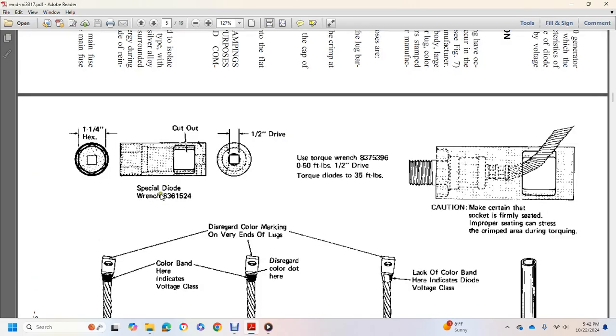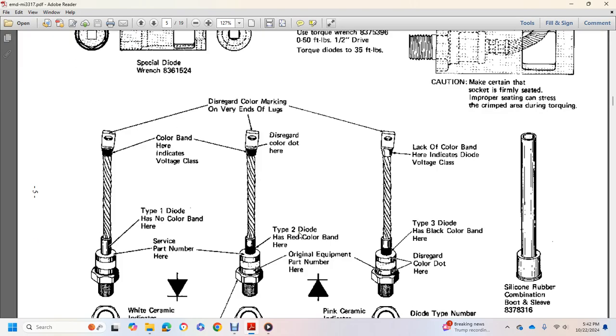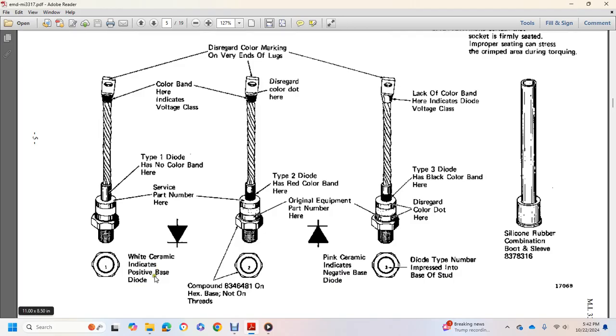Okay, this shows the special diode socket, a 1 1/4 inch hex cutout with a 1/2 inch drive for the torque wrench, for torquing the diodes up to 35 foot-pounds of torque. Make sure the socket is firmly seated; improper seating can stress the crimped area during the torquing. The white ceramic indicates the positive diode, with a compound hex bolt, not threaded. The pink ceramic indicates the negative diode. The type number is stamped on the stud, with the silicone rubber combination boot and sleeve. You have type 1, type 2, type 3.